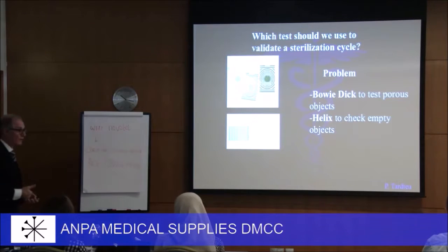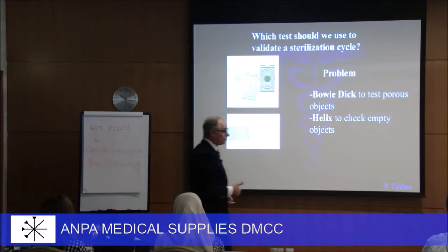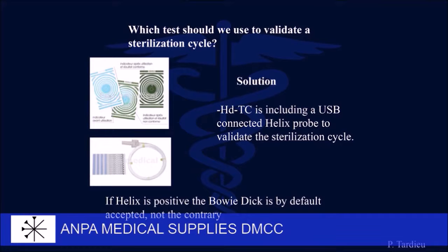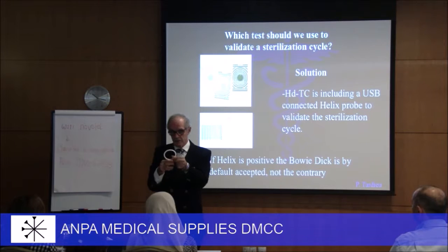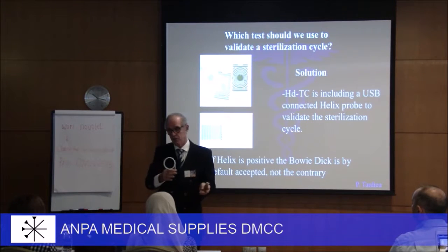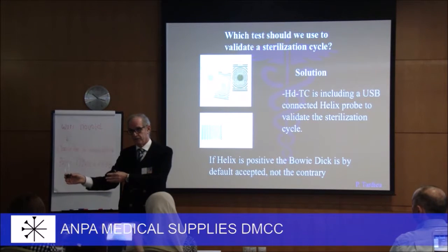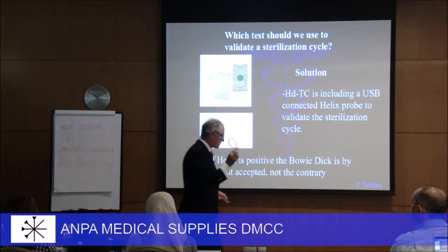This is why we decided to go to a helix system. We put this helix system in every sterilization cycle. It includes a battery and a sensor, and it captures all the details of the sterilization. Then you put it on a stand and import the data to your computer. Okay? So that's the helix.